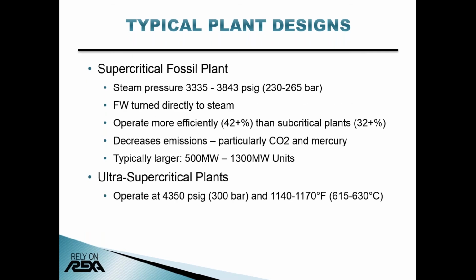Supercritical boiler technology came later in the 1950s. A supercritical boiler operates above the critical pressure of water where there is no difference in the density of water and steam. There is no steam drum. Water is immediately turned to steam in the tubes. Circulation is once through the tubes, accomplished by using a pump. Better grades of materials are needed to accommodate these higher pressures and temperatures. The preference in supercritical boilers is that they are more efficient than their subcritical counterparts at greater than 42% and have lower emissions. These plants are typically larger and above 500 megawatts.